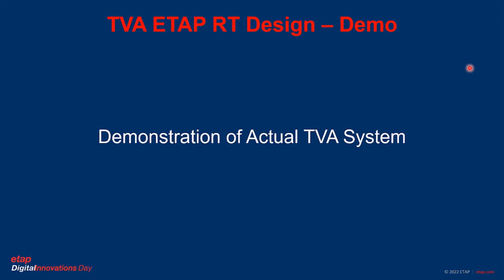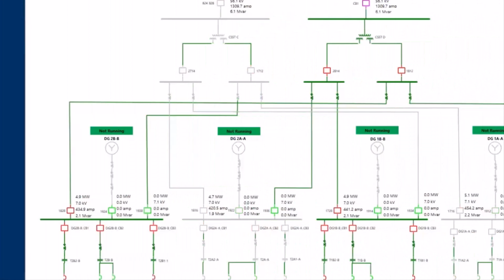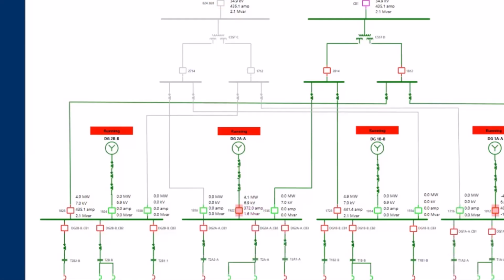Now, even though we haven't actually installed a system yet, by using the simulator, I can demonstrate what our system would look like. So here's a short simulation of an event, which is a loss of offsite power. You can see the diesel generators have started up. Soon you'll see their breakers close to connect them to the shutdown boards. There it goes. I've got the diesels connected on the buses that lost offsite power, and you'll see the diesel generators picking up load. Again, this is close to real. It's not exactly what you would see in the plant, but just enough to demonstrate the capability of the system and kind of give an idea of what the human-machine interface would look like.